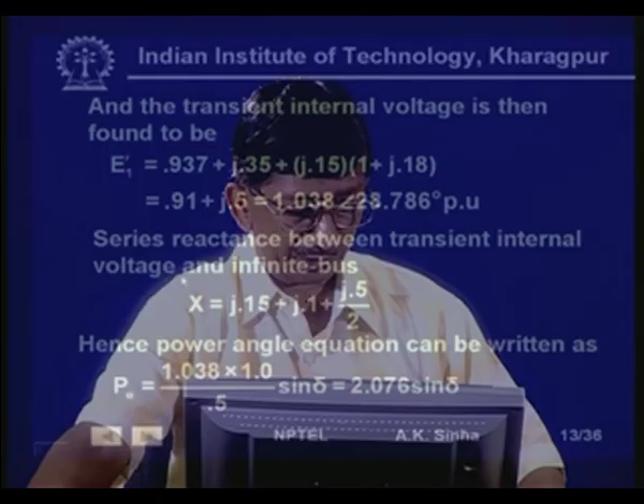degrees. Now, the series reactance between the transient internal voltage and the infinite bus, that is between E dash and the infinite bus, is equal to how much? This is 0.15, which is the transient reactance of the machine, plus 0.1, which is the transformer reactance, plus 0.5 parallel 2 lines. So, 0.5 by 2. Total transfer reactance is 0.15 plus j 0.1 plus j 0.5 by 2. This comes out to be 0.5. So, the power angle equation for the machine can now be written as E V by x into sin delta. This is equal to 2.076 sin delta.